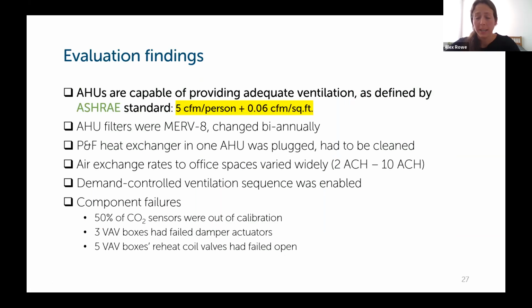So then back to the findings of the evaluation. Based on the preliminary airflow testing report and engineering calculations, the engineer determined that the air handlers are capable of providing adequate ventilation as defined by the ASHRAE standard of 5 CFM per person plus 0.06 CFM per square foot. They also determined that the boiler and chiller have adequate capacity for conditioning the outside air on maximum outside air, on design heating and cooling days.